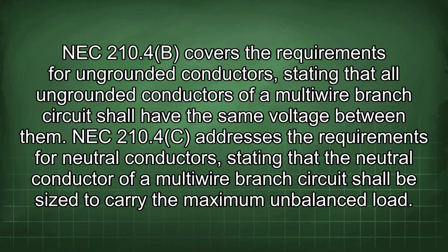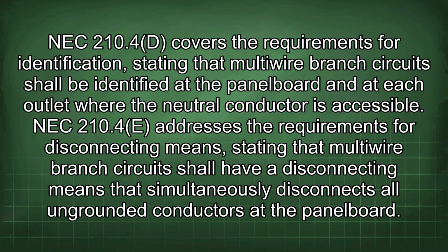NEC 210.4c addresses the requirements for neutral conductors, stating that the neutral conductor of a multi-wire branch circuit shall be sized to carry the maximum unbalanced load. NEC 210.4d covers the requirements for identification, stating that multi-wire branch circuits shall be identified at the panel board and at each outlet where the neutral conductor is accessible. NEC 210.4e addresses the requirements for disconnecting means, stating that multi-wire branch circuits shall have a disconnecting means that simultaneously disconnects all ungrounded conductors at the panel board.